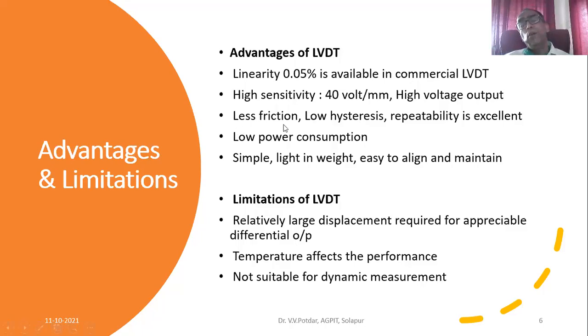Very less friction, low hysteresis, excellent repeatability - all these properties we've already seen. Hysteresis is an error, isn't it? If you remember, hysteresis occurs when I give input in incremental ascending order, and when I give input in descending order, the error is very minimal in case of LVDTs, because stray magnetizing currents remain very low. So this LVDT tends to give low hysteresis error and very less friction because moving parts are very few, and repeatability is excellent. What do we call repeatability?